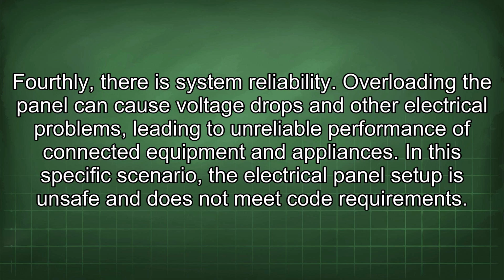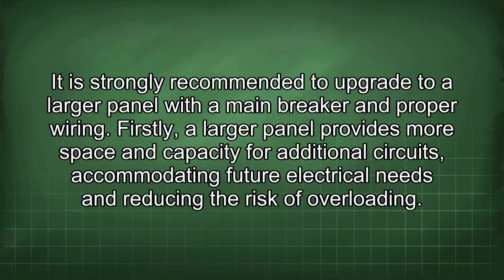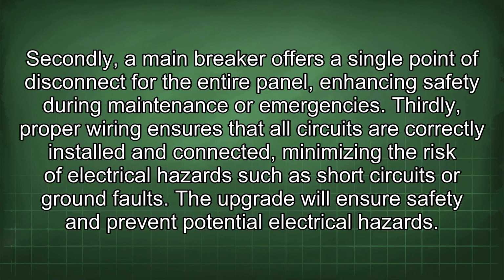In this specific scenario, the electrical panel setup is unsafe and does not meet code requirements. It is strongly recommended to upgrade to a larger panel with a main breaker and proper wiring. Firstly, a larger panel provides more space and capacity for additional circuits, accommodating future electrical needs and reducing the risk of overloading. Secondly, a main breaker offers a single point of disconnect for the entire panel, enhancing safety during maintenance or emergencies.